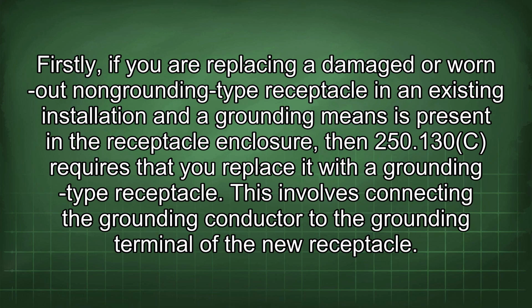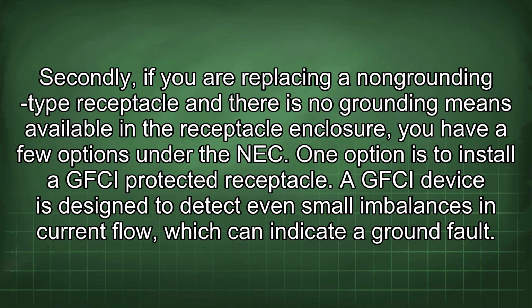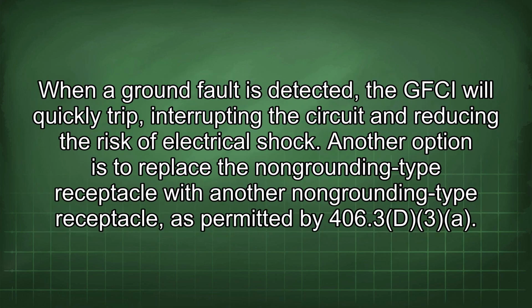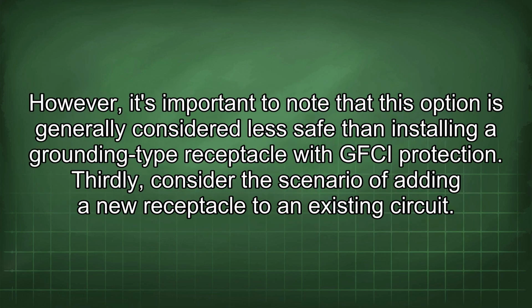Firstly, if you are replacing a damaged or worn-out non-grounding type receptacle in an existing installation and a grounding means is present in the receptacle enclosure, then 250.130c requires that you replace it with a grounding type receptacle. This involves connecting the grounding conductor to the grounding terminal of the new receptacle. Secondly, if you are replacing a non-grounding type receptacle and there is no grounding means available in the receptacle enclosure, you have a few options under the NEC. One option is to install a GFCI protected receptacle. A GFCI device is designed to detect even small imbalances in current flow, which can indicate a ground fault. When a ground fault is detected, the GFCI will quickly trip, interrupting the circuit and reducing the risk of electrical shock. Another option is to replace the non-grounding type receptacle with another non-grounding type receptacle, as permitted by 406.3d3. However, it's important to note that this option is generally considered less safe than installing a grounding type receptacle with GFCI protection.